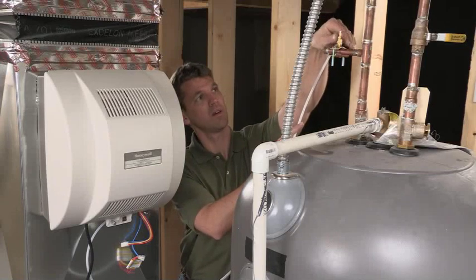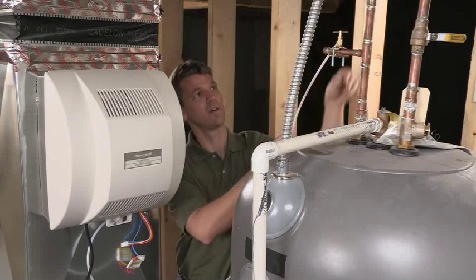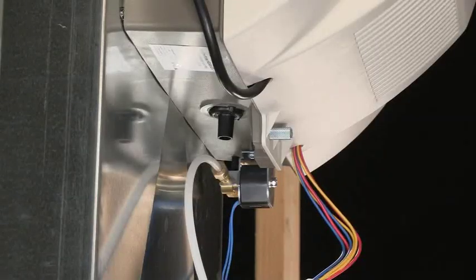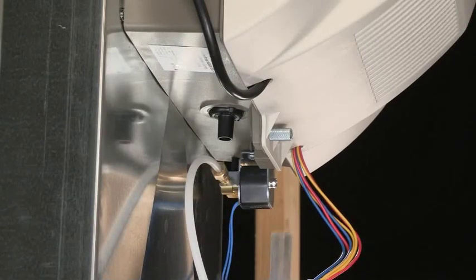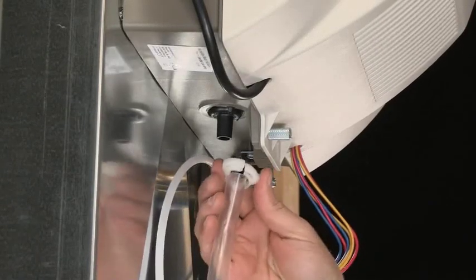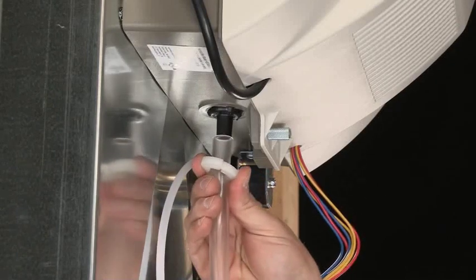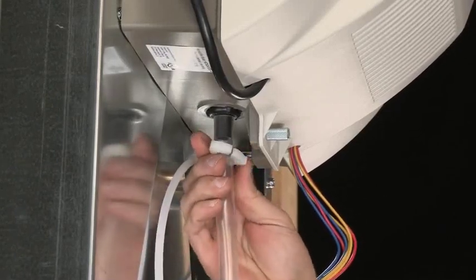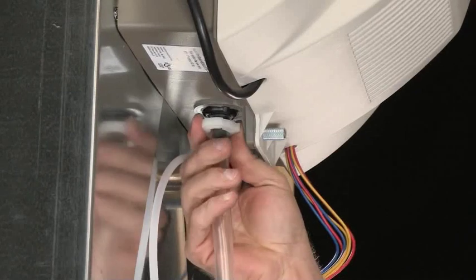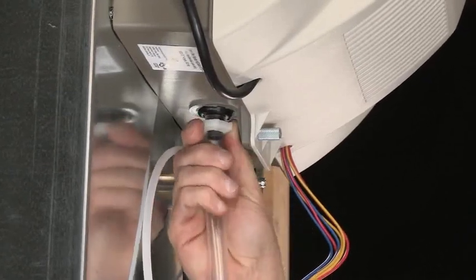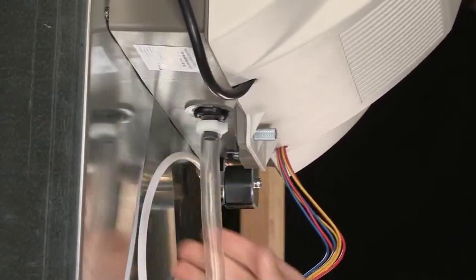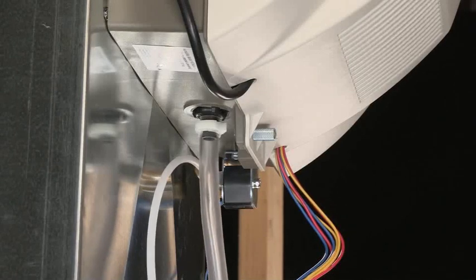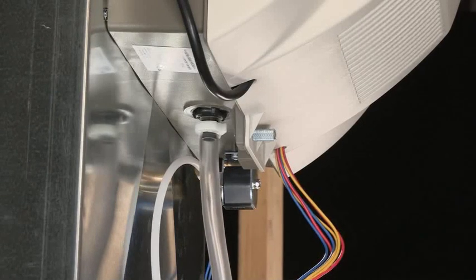Now that we've hooked up the supply water, we'll connect the drain tubing. Slide the drain clamp over the tubing and push the tubing over the drain fitting on the humidifier. Hand tighten the clamp around the tubing to secure it to the humidifier drain. The clamp is tightened by compressing the two sides together so that one side fits into the rigid groove on the other side.